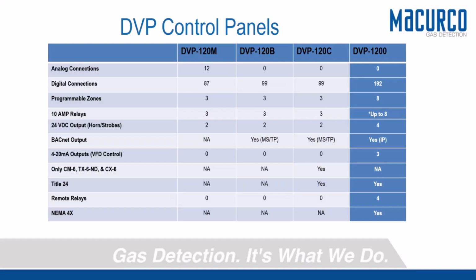If you're on the fire side and you know a little bit about building automation or the HVAC world, you'll see this comment right here, BACnet MSTP or BACnet IP. Huge discrepancy between the two. If you have a protocol that's BACnet MSTP, you have to pretty much go MSTP unless you have a converter, which can be kind of costly. But we have panels for both options. If you're in California, both of the panels are Title 24 compliant. They have the settings in there, the testing features in there. You should be good to go. But again, you can always tie this back to a fire panel just as simply as well.